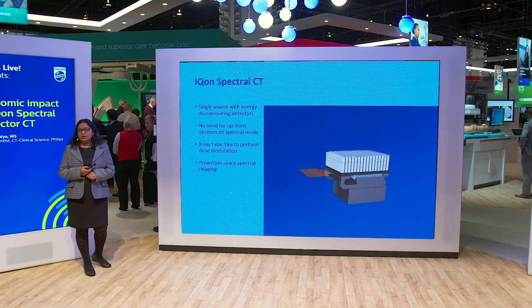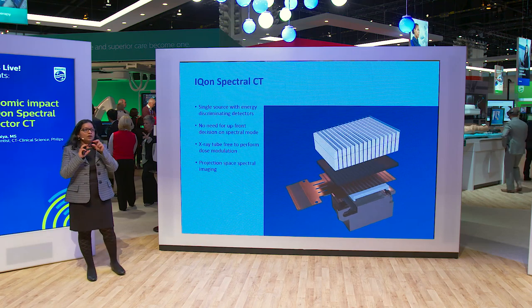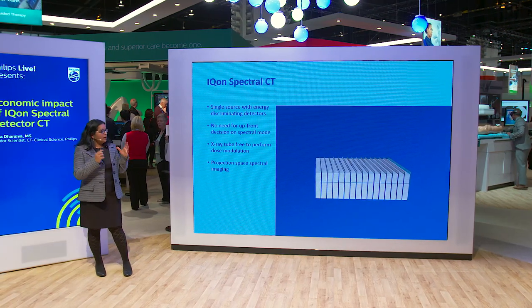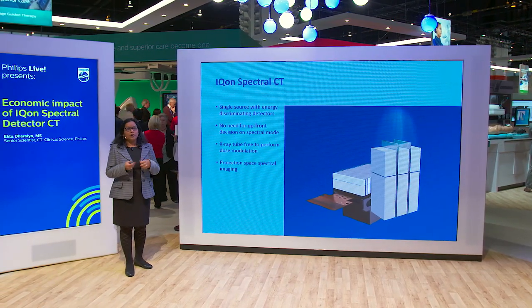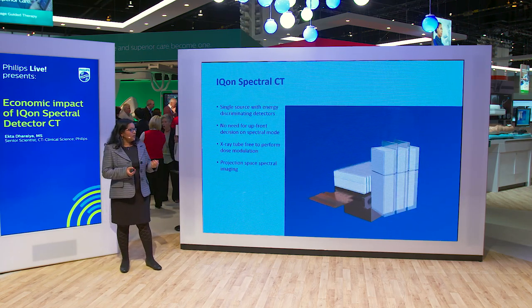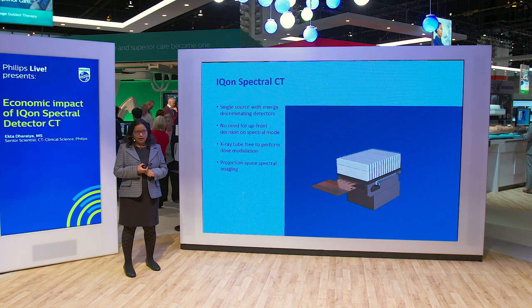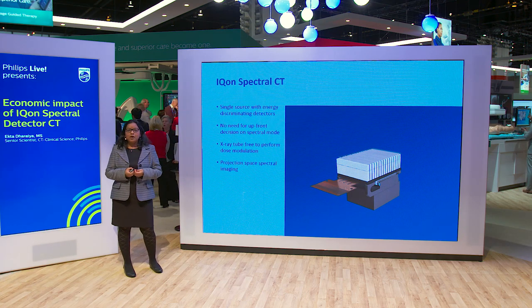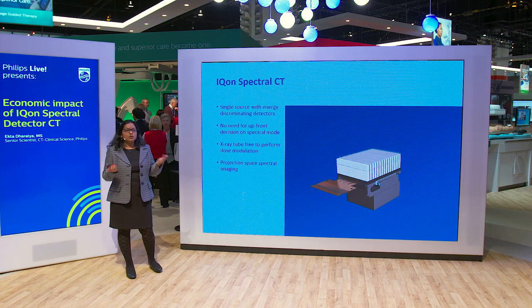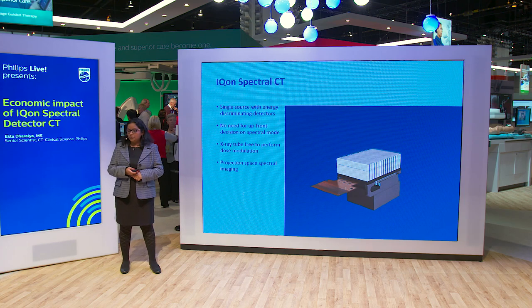IQon Spectral CT is a single-source CT with energy-discriminating detectors. It has a dual-layer detector — the top layer absorbs low-energy photons while the bottom layer absorbs high-energy photons. The data from the two layers can be combined to create a conventional image as well as what we call a spectral-based image. These spectral-based images can then be used to create different spectral results. Since the data from the two layers are perfectly aligned, you get true projection-based spectral imaging. And since this is a detector-based system, your tube is free to do dose modulation, and you don't have to make a decision upfront to scan a patient in spectral mode.